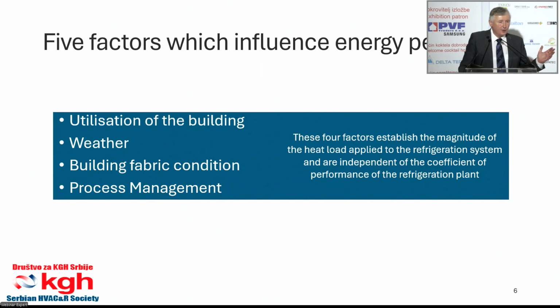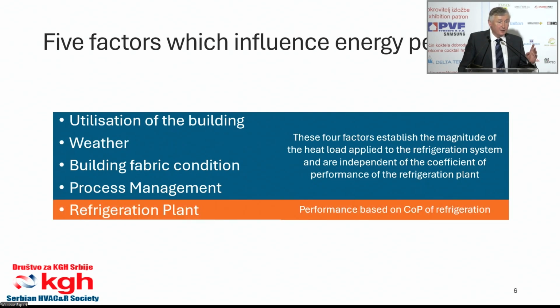These 4 factors all determine the magnitude of the heat load. If the insulation is poor, there'll be more heat gains. If product comes in warm, there'll be more heat to extract. And they're independent of the COP of the fridge plant. So it doesn't matter how good or bad the fridge plant is. If you don't get these 4 things right, your energy bill will be high. But the 5th one is the refrigeration plant, only one out of the 5 factors.